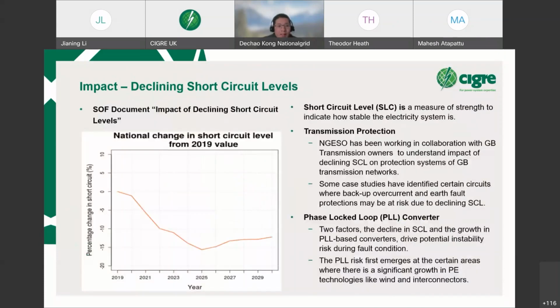The second one is about short circuit levels. As I mentioned, another impact is that it will trigger a decline in the short circuit level with the high integration of power electronics and the declined portion of synchronous generators. As you know, network protections are designed to detect and safely isolate faulty equipment as quickly as possible, limiting the fault effects on the wider system.